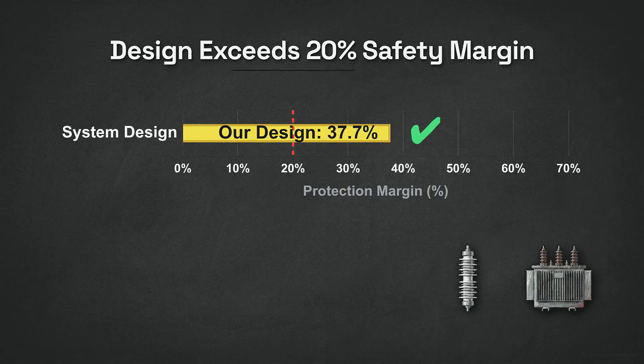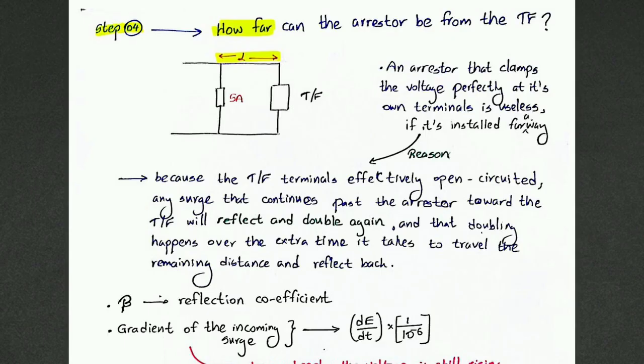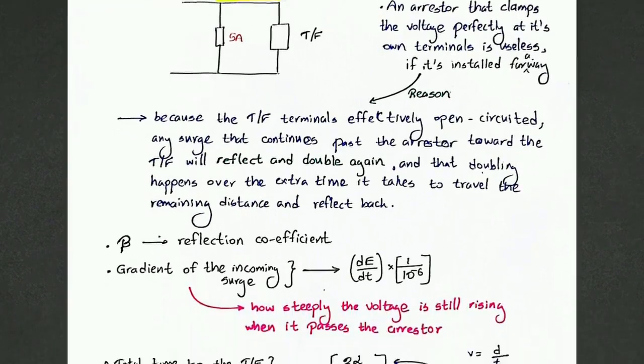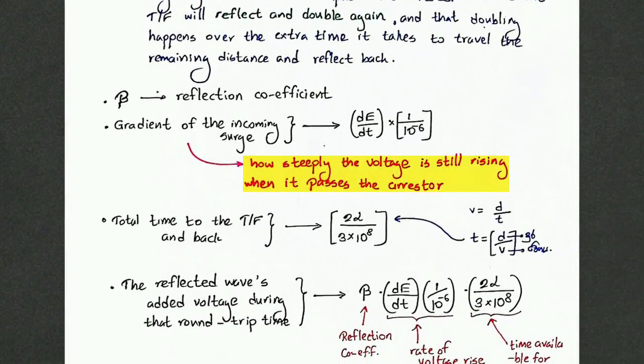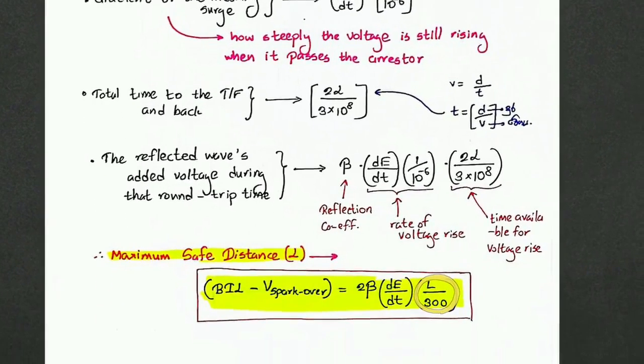There is one final constraint. Step 4, the maximum safe distance. An arrestor with perfect specifications can only protect the equipment within a specific physical range. The physical distance, represented by L, creates a delay. The further the distance, the more time the reflected wave has to steepen and build up additional voltage before the arrestor has a chance to clamp down. We calculate this boundary using a time fraction based on the speed of light.